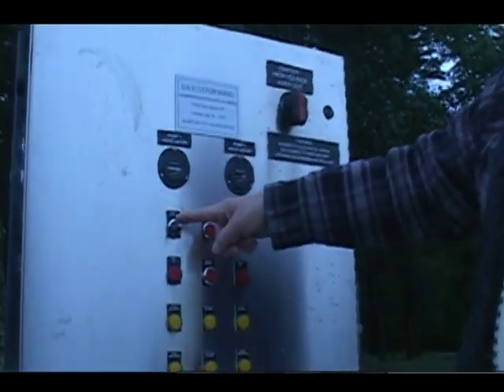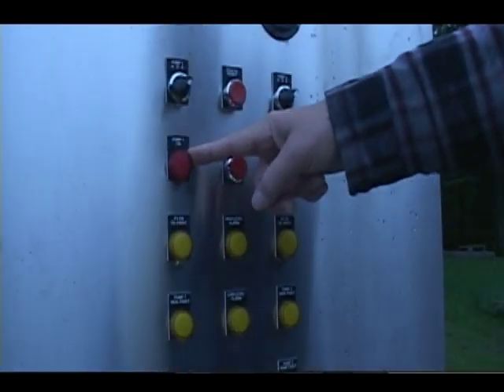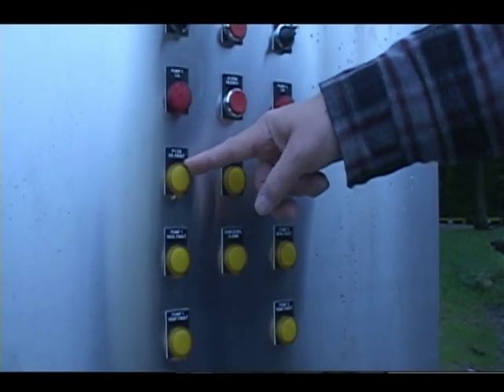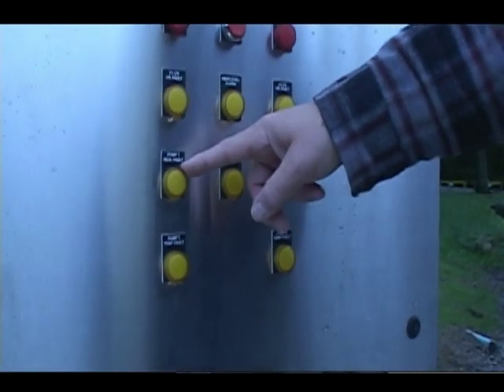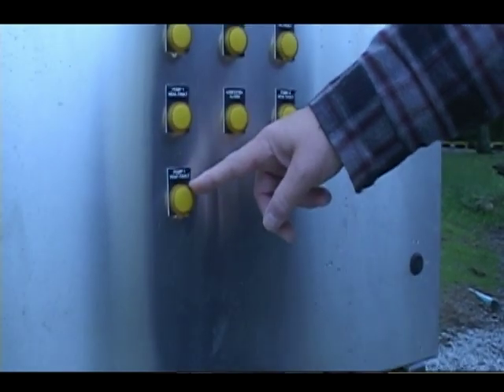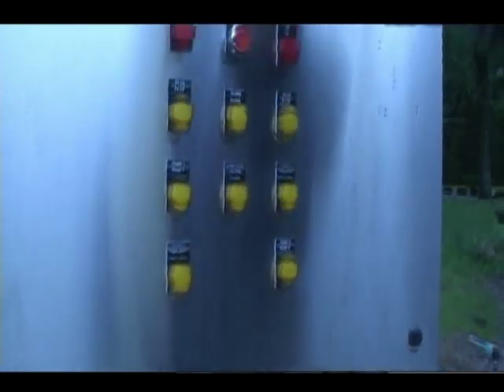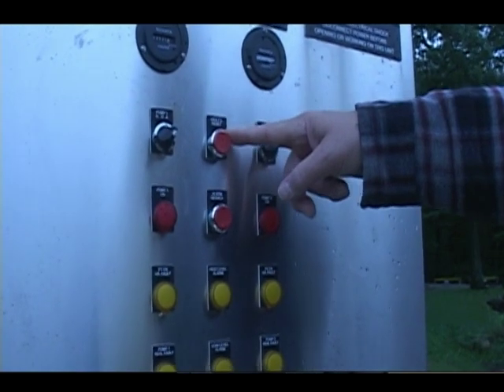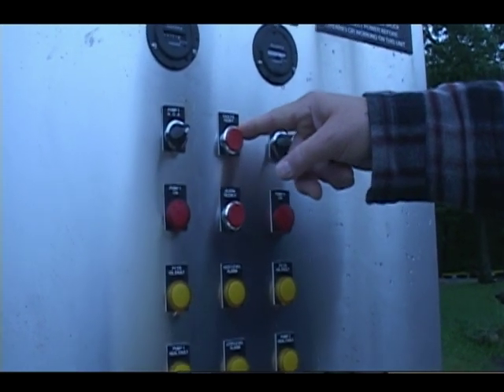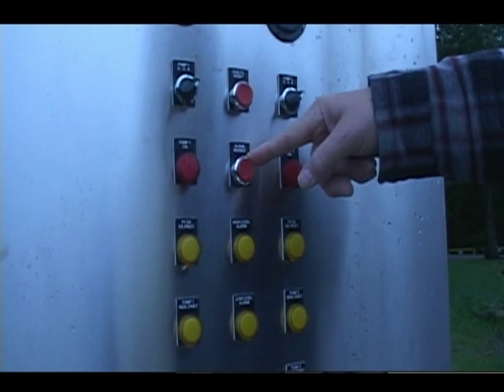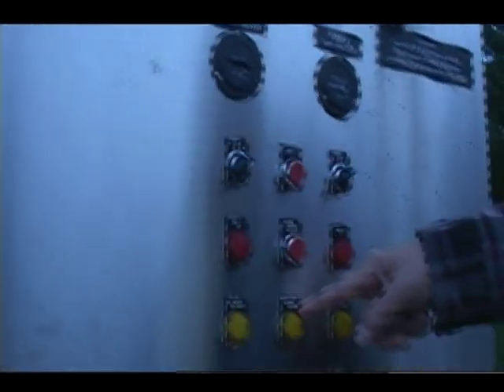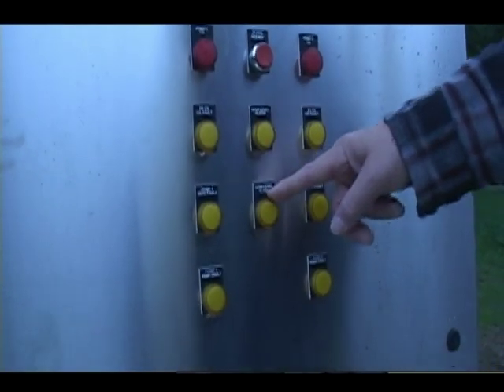Each of the pumps are set up identical to each other. Each of them has an hour meter, hand-off-auto selector switch, a pump on indicating light, a pump circuit breaker overload fault, a seal fault indicator, and a temperature fault. A fault reset button is used for both of them. Alarm silence silences the alarm horn, which is located on the side of the panel. Alarms: a high level alarm and a low level alarm.